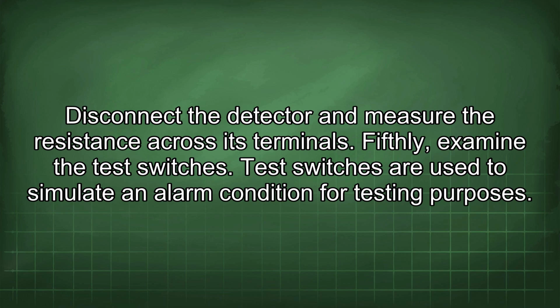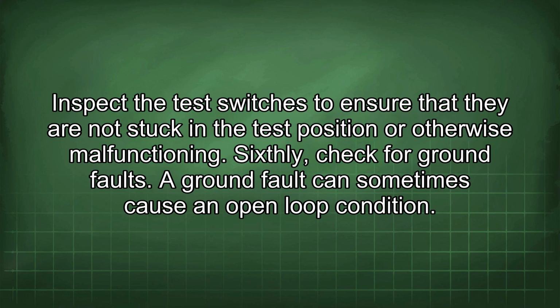Fifthly, examine the test switches. Test switches are used to simulate an alarm condition for testing purposes. Inspect the test switches to ensure that they are not stuck in the test position or otherwise malfunctioning.